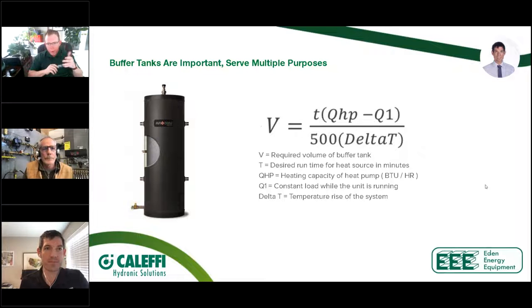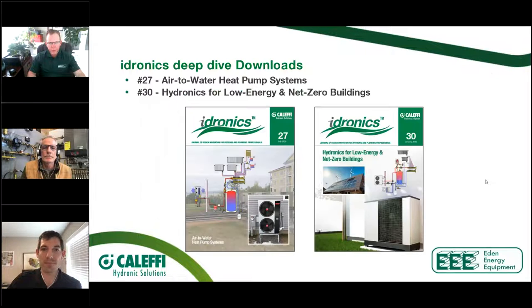But again, remember what Bob said at the very beginning of this, and I repeated, and Max repeated, if we can have this equipment run low and slow all the time and never shut off, that's a really efficient functional system. So just make sure you're not applying buffer tank math for boilers to heat pumps because they are a little bit different. And then also understand every buffer tank's a little bit different. I love this buffer tank because of how it's piped. I'm not going to get too crazy in the details, but I've got a buffer tank that acts as a great hydraulic separator. It's perfectly stratified. I know I'm delivering the hottest water at all time. Whereas if I had ports coming at all these oddball places, I'd have to be thinking about dip tubes and how I'm piping it and how it stratifies. So go for simplicity. Try to make your systems work well.